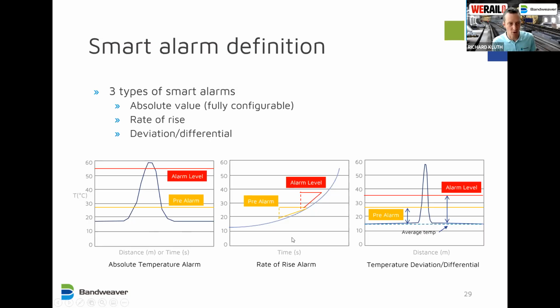If we move to the rate of rise, this corresponds to how quickly the temperature rises within a defined time period, which is typically a minute. And one of the advantages is this can detect much earlier than the absolute temperature alarm. Typically for a tunnel, rate of rise would be something around 9-10 degrees C per minute. The absolute temperature may be 58 degrees. If we think the ambient temperature of a tunnel is anything from 10 to 30 degrees on average, you can detect much earlier than before the temperature has to reach 58 degrees. It's a very efficient way of alarming and buying valuable time.